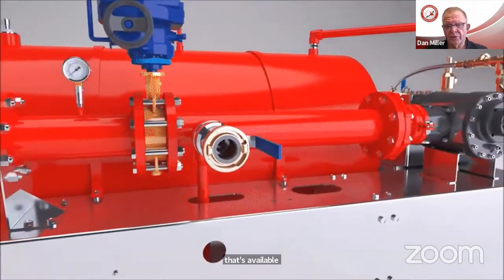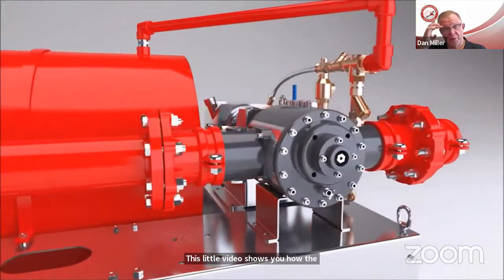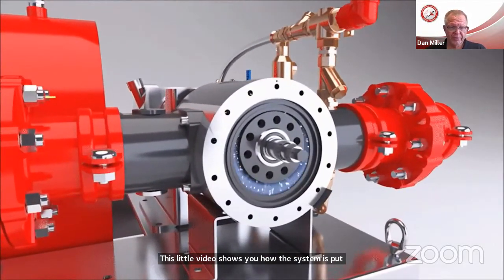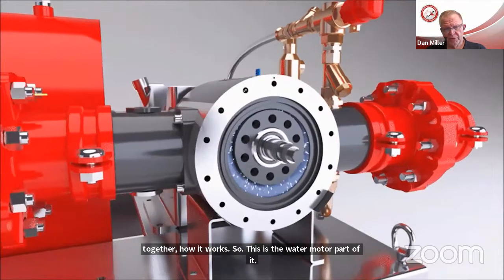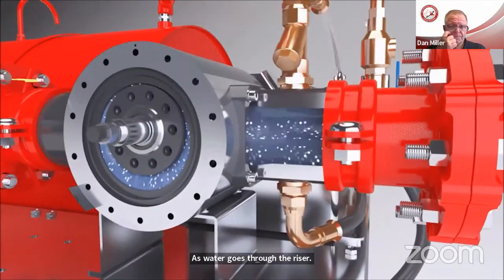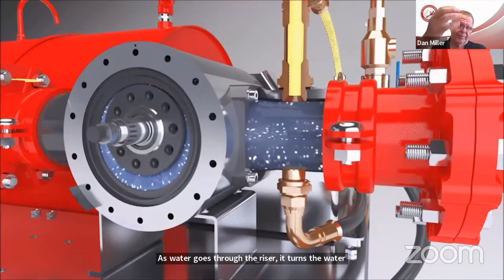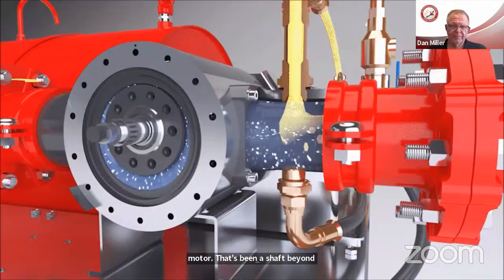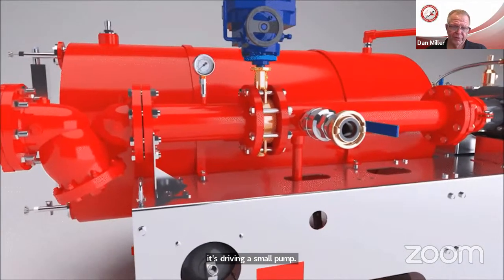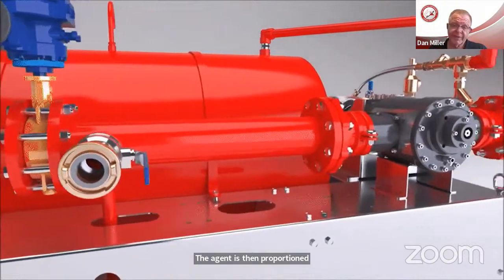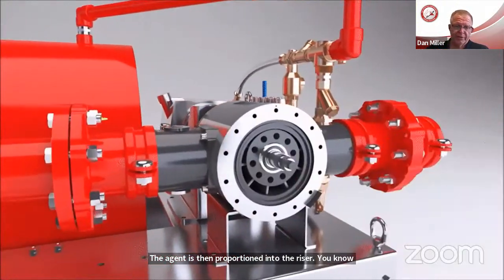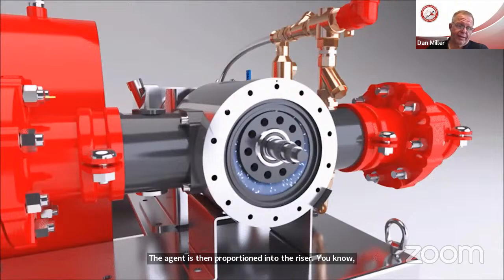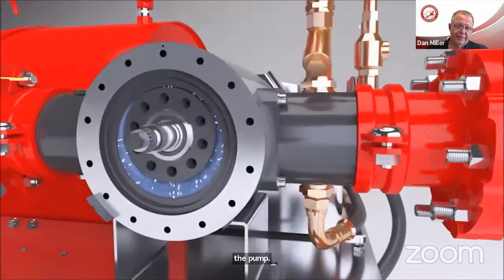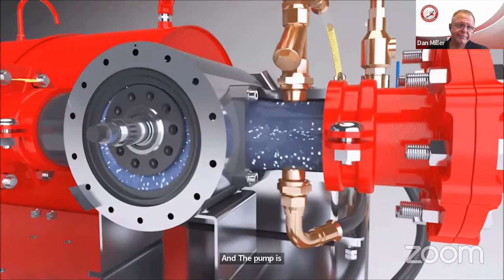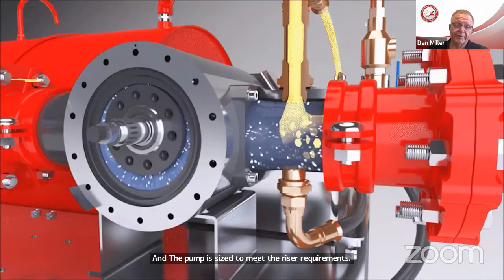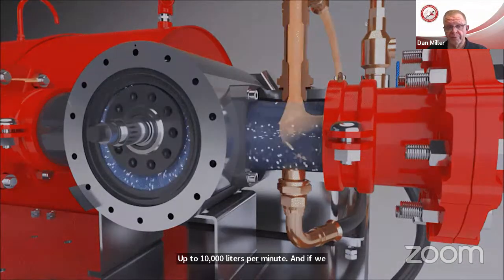This little video shows you how the system is put together, how it works. So this is the water motor part of it. As water goes through the riser, it turns the water motor. That spins a shaft. Beyond where you can see, it's driving a small pump. The agent is then proportioned into the riser at the correct rate, simply based on the RPM of the pump. And the pump is sized to meet the riser requirements, up to 10,000 liters per minute. And if we need to go over that, we just put them in tandem.